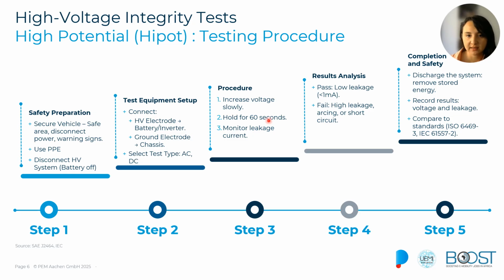At that point, we have to watch that there are no leakage currents, or that the leakage current stays below the certain threshold that the standard says, and that the insulation is in general in good shape. After that, we go to the fourth step, where we analyze the result. So in that case, the pass condition will be to have a low leakage current, to not have any arcing or sparking, or any sign of deterioration in the insulation. After the test, we discharge any stored energy, and we record the results and compare them with the standards that we are using, and the criteria established by those standards is compared to the results that we obtain.